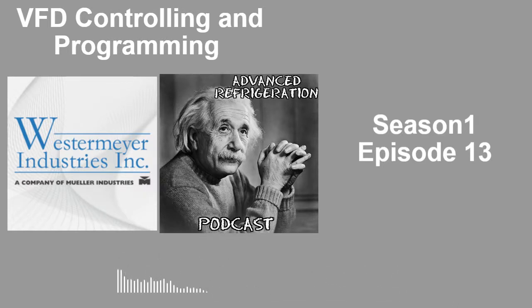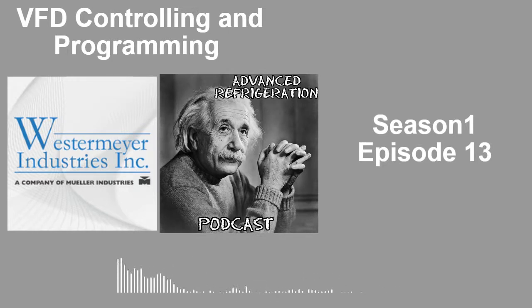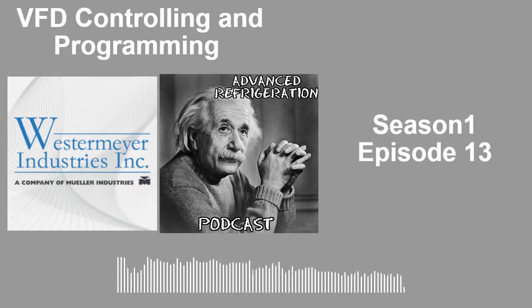So that'll be controlling that compressor. You could have a bypass set up. It depends on the customer whether they have one or not. You should. That compressor is controlled off a 0 to 10 volt signal or a 10 to 0 volt signal, depending on how it's set up. Your suction group is going to be sending that control to it. Now, something you've got to watch for is oil pressures. You don't want to be at the bottom range of your run the entire time. You could create some oil issues.